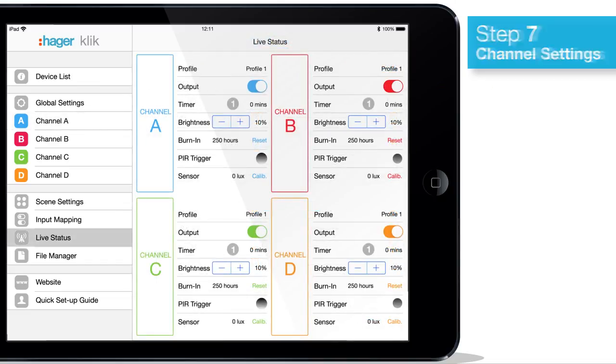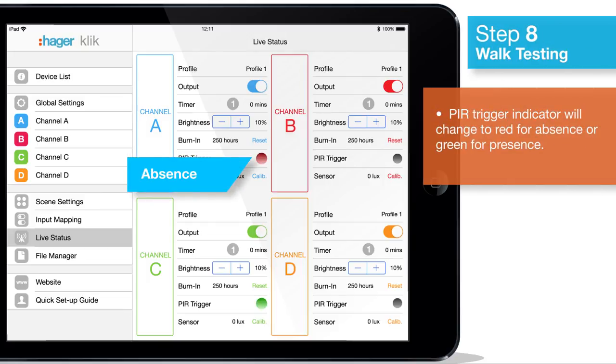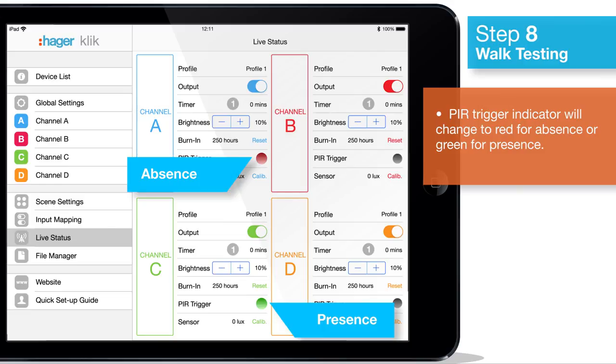Conducting a walk test allows you to test the detection area and check if the LCM is set to absence or presence. When the occupancy sensor detects movement, the PIR trigger indicator will change colour.